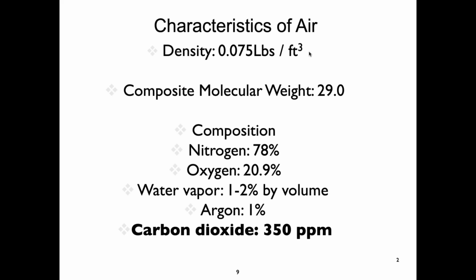What was it reading, roughly? 1300. Where did all that extra carbon dioxide come from? Right, from us. We're converting oxygen to carbon dioxide. Normally, if we have good ventilation in this room, it will control the level of CO2 building up in the room. So the fact that we're not controlling the level of CO2 building up in this room means we're not controlling any other VOCs that might be entering this room.